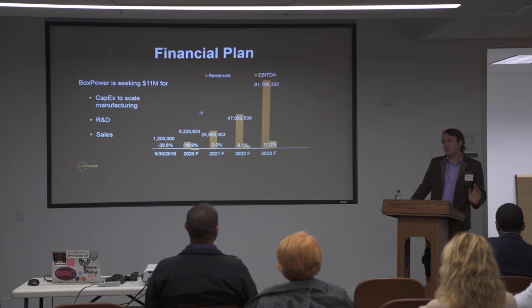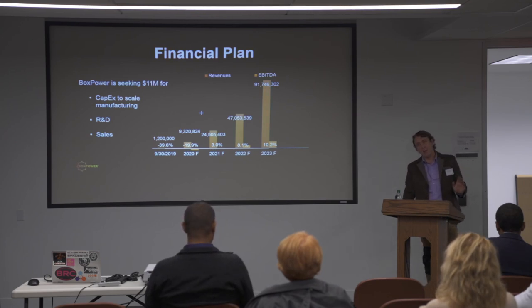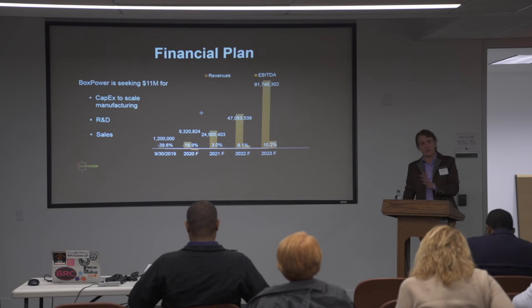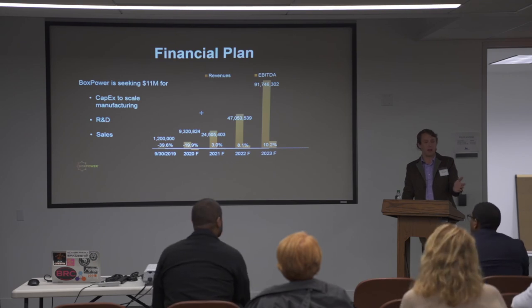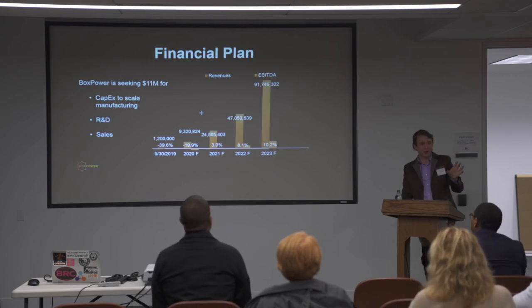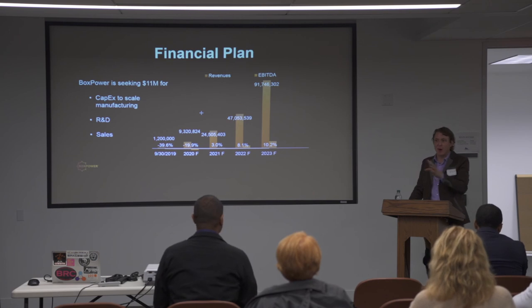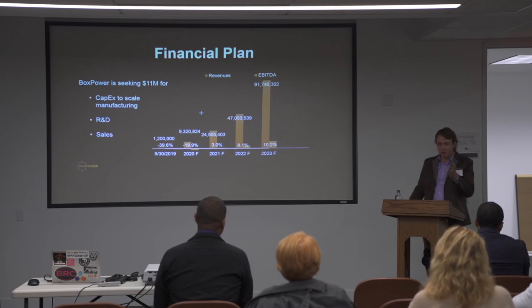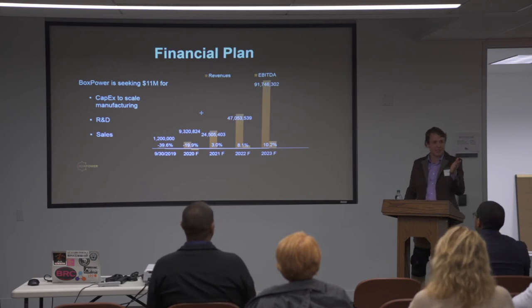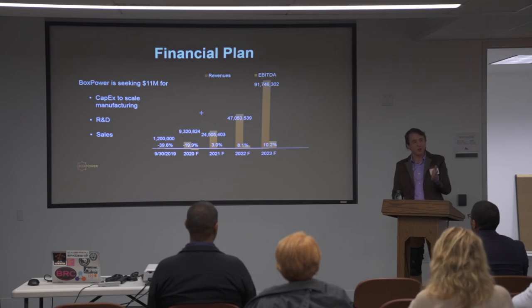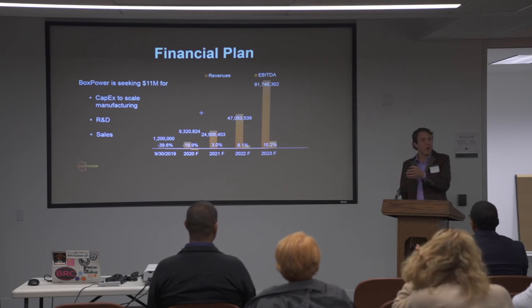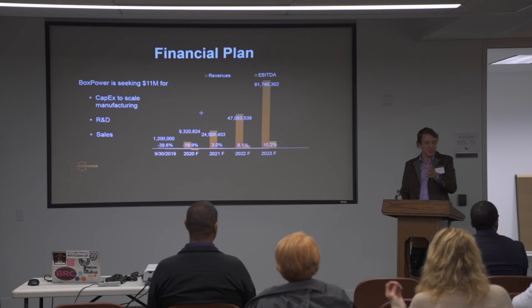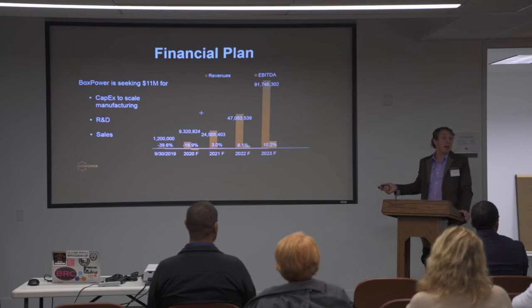Yeah, so we design our batteries at max system output capacity, which gives only a 2-hour backup. Now, granted, people are very rarely using the max output capacity of the system. Generally power factor utilization rates are 20 to 30%, which gives you a 6 to 8 hour backup on the system capacity. But we provide a hybrid system.